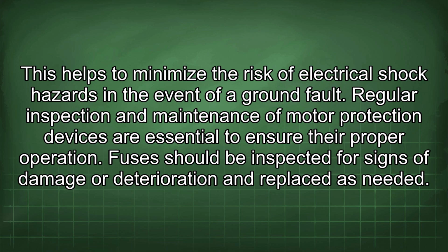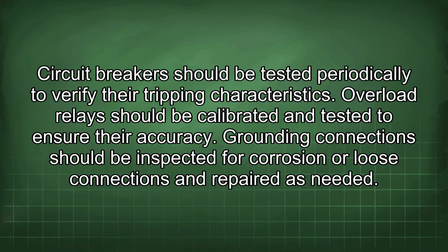Regular inspection and maintenance of motor protection devices are essential to ensure their proper operation. Fuses should be inspected for signs of damage or deterioration and replaced as needed. Circuit breakers should be tested periodically to verify their tripping characteristics. Overload relays should be calibrated and tested to ensure their accuracy. Grounding connections should be inspected for corrosion or loose connections and repaired as needed.